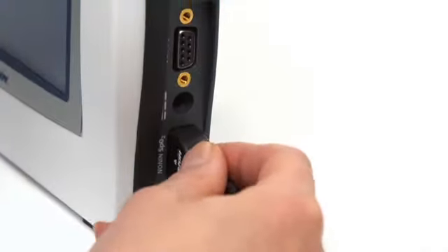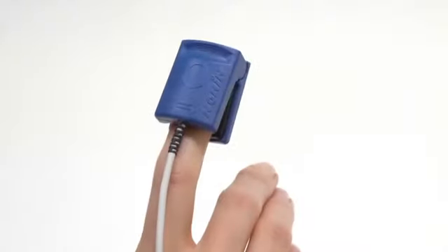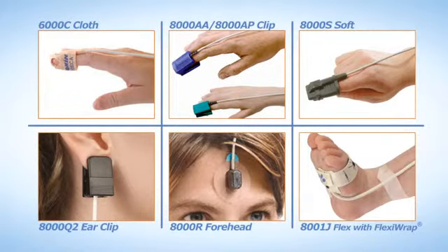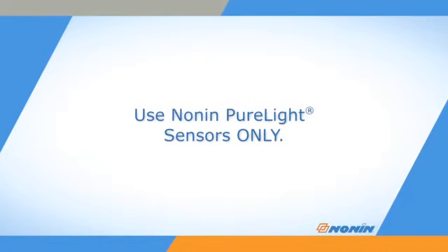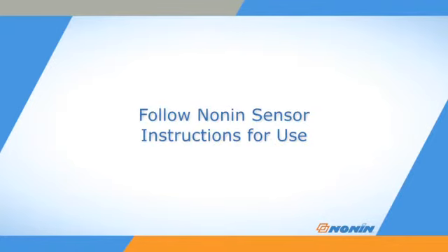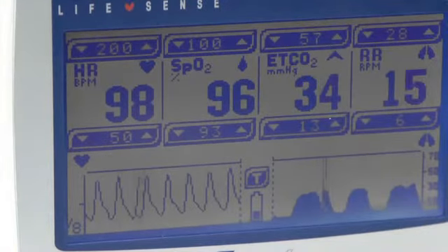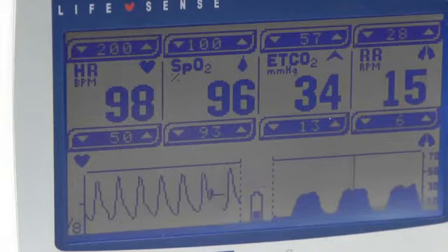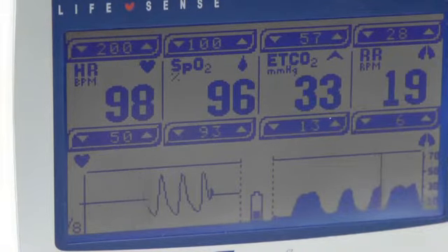The LifeSense capnography and pulse oximetry monitor has a cable connector on the right side of the monitor to attach a NONIN PureLight brand SpO2 sensor. The LifeSense monitor is designed for use with NONIN brand sensors only. Do not use the LifeSense unit with other brand sensors, and follow the sensor instructions for use for proper sensor placement and care. SpO2 and pulse rate display on the left side of the screen along with the ET CO2 and respiration data.